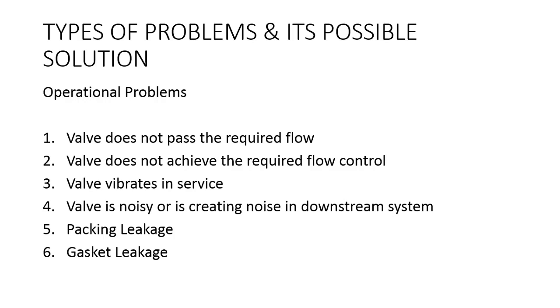Third is the aerodynamic noise. It can be generated due to high velocity in gas or flashing. Path or source treatment of noise must be considered if required.